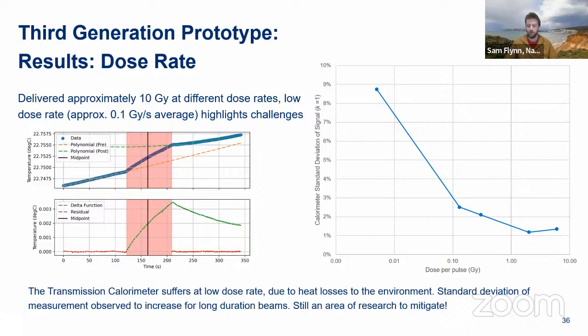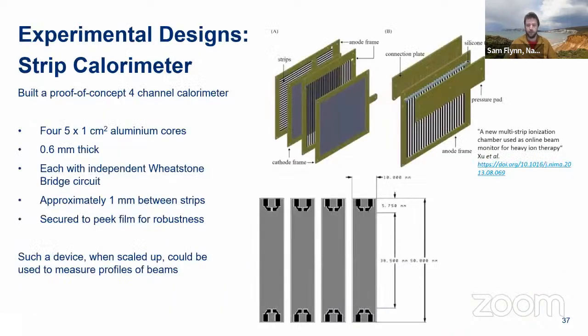With this in mind, we believe we've done a lot to prove that you can make a calorimeter into kind of an ionization chamber. So we had a bit of creative thought about what more we can do to make a calorimeter like an ion chamber. What would be useful for the community? If you aren't familiar with strip detectors, they're very common in ion beam therapy, and it's just lots of independent, electrically isolated ionization chambers, which you can use to tell the position and size of a radiotherapy beam.